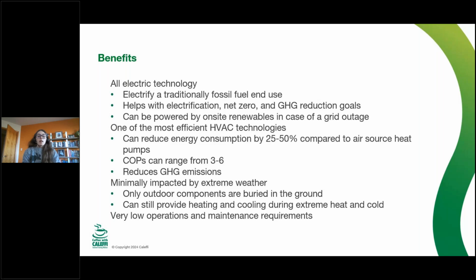And then another really cool resiliency piece of ground source heat pumps is that they're minimally impacted by extreme weather. So for example, if you have a hurricane that comes in and demolishes your building, well, hopefully that's not the case, but the ground heat exchanger is buried in the ground, and that system is probably going to weather that storm just fine. We've actually had some stories from resource efficiency managers, REMs, at installations, where they've had other systems sustain some really bad damage from big storms, from hail, from lightning, and their ground source heat pump system continues to work. So that's really cool. And they can also still provide heating and cooling during extreme heating and cold events, because of those stable ground temperatures.